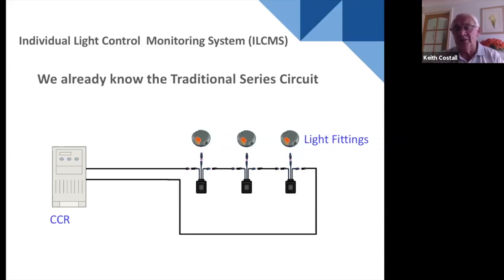So every single AGL circuit on every airport all over the world is different. It has a different length and a different number of isolating transformers in it. So we calculate, and it's the earth leakage calculation that we calculate first. What I mean by that is that for every transformer, we are allowed to have 2 microamps leakage to earth in our field circuit because of where it lives. And for every 100 meters of primary cable in a circuit, we're allowed to have 1 microamp leakage to earth. Now, bear in mind there are multiple lengths of primary circuit and multiple numbers of light fixtures, hence multiple numbers of transformers, because it's 1 light, 1 transformer normally. So we calculate it.